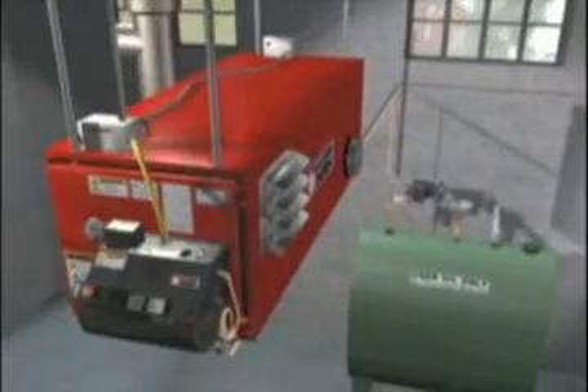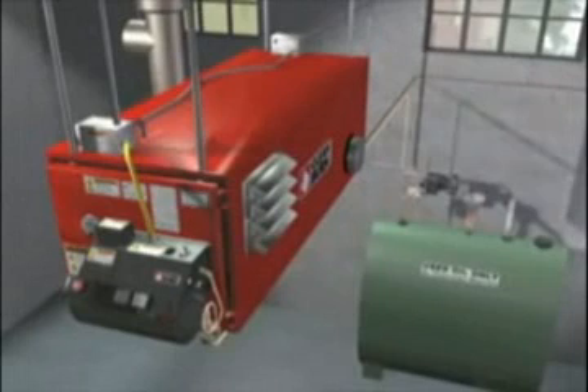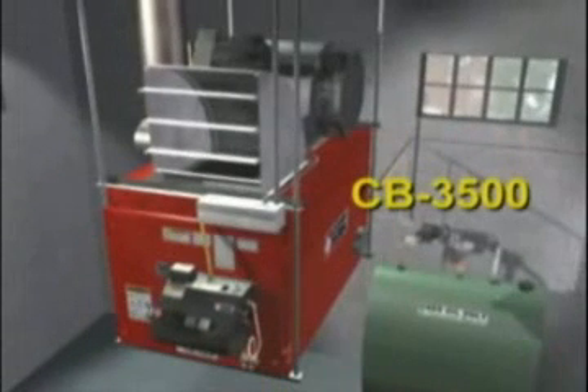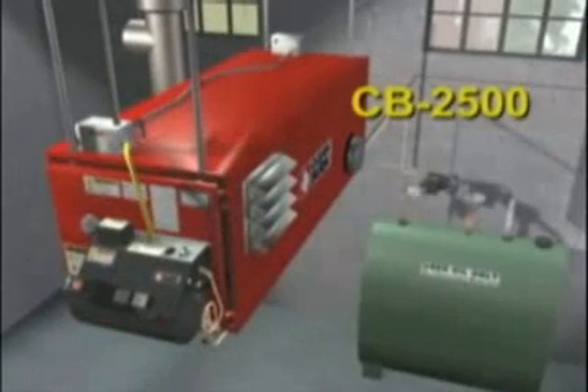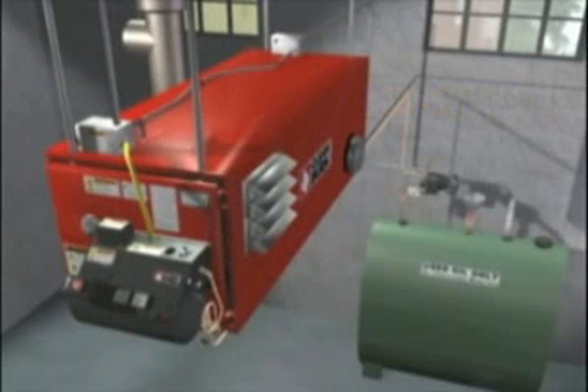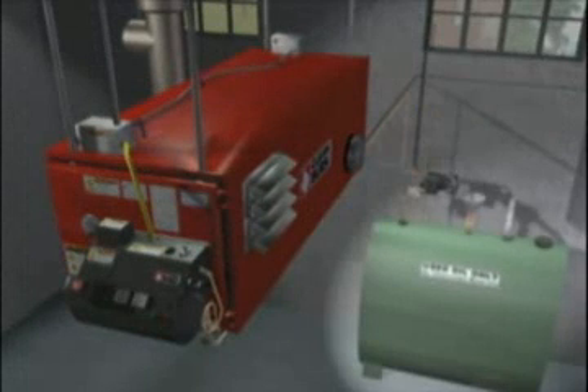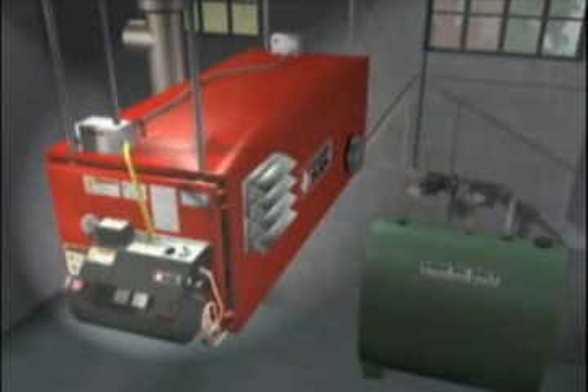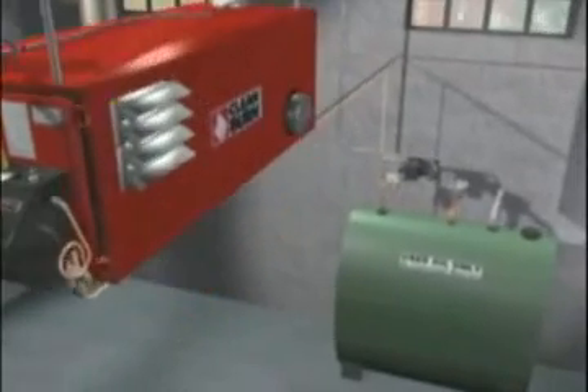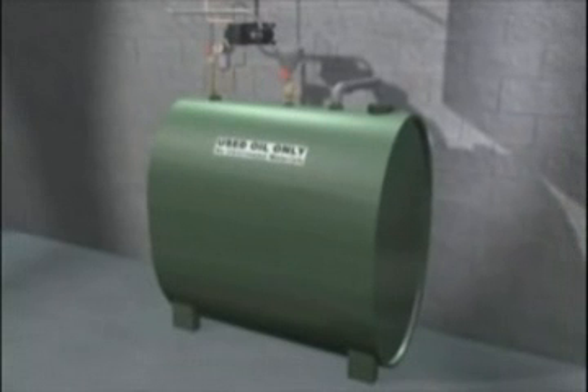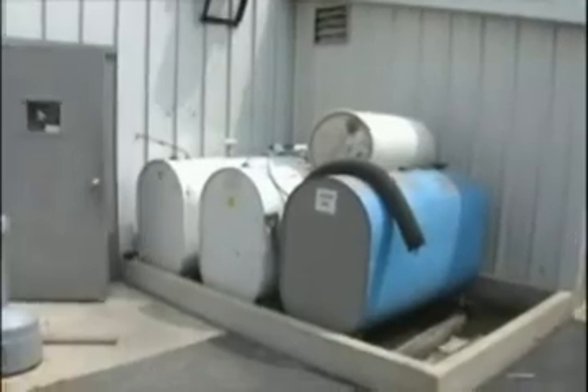CleanBurn manufactures a variety of furnace models, with one just right for your shop. This is the CB3500, which is one of CleanBurn's larger models. We will use it along with the popular CB2500 to show what makes CleanBurn so efficient and long-lasting. A CleanBurn heating system is comprised of 3 sections: the oil storage tank, the oil pump assembly, and the furnace unit itself. The waste oil used to fuel the CleanBurn furnace is held in an oil storage tank. An existing storage tank can be used, or your CleanBurn distributor can provide a storage tank appropriately sized to your operation. It can be located either inside or outside your shop.